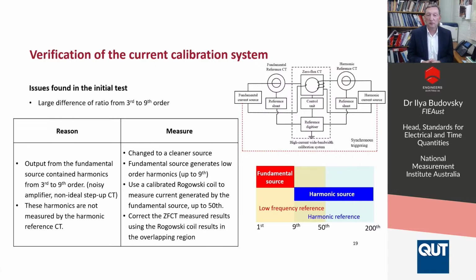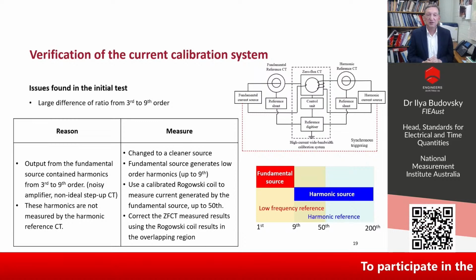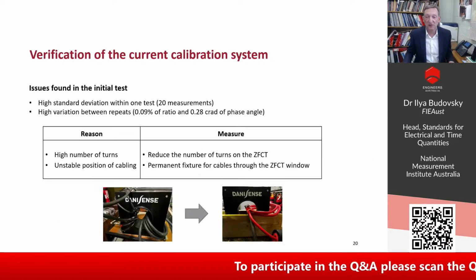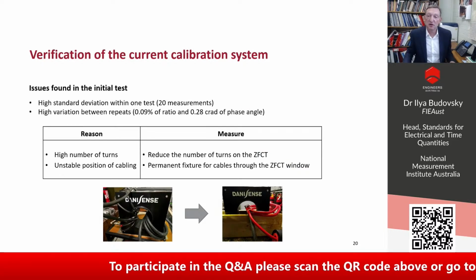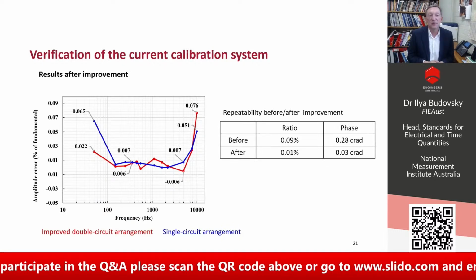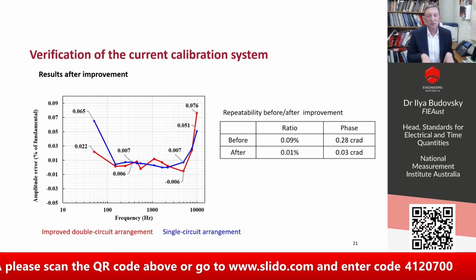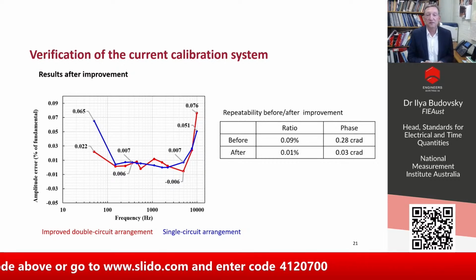So what we have done then is we've calibrated the reference that was used for 50 hertz measurement. We've calibrated it for harmonics, and then we could adequately measure all of them. And actually, in the later design, we thought, all right, why don't we actually use the 50 hertz source to produce some harmonics? And that was very successful. So it now produces harmonics up to the 9th. All of this, as shown here, led to very, very nice agreement between the two methods. And it says that both of them work, and we can calibrate the reference separately.